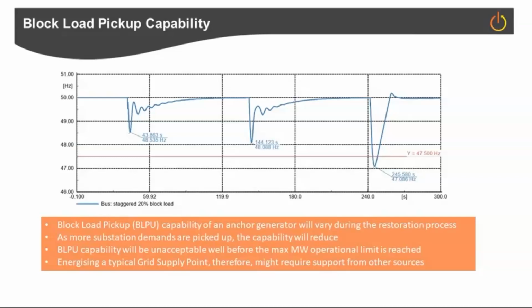And the kind of resolution of those blocks. Now, the smallest possible resolution is a 33 to 11 kV distribution feeder to bring on customer demand. There's that cold load pickup effect as well, which I mentioned earlier, so you could actually see twice the amount of load you'd expect on that feeder. So you get this limitation utilizing the initial black start unit, the initial anchor generator. There's a limitation around block load capability, so you have to be wary of that, and there's definitely a need to get help from adjacent DERs. So that's one point I wanted to make. That's something our studies have uncovered.